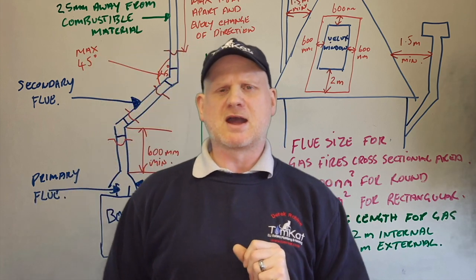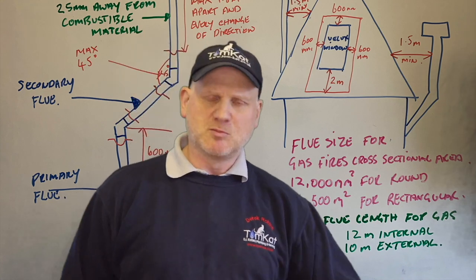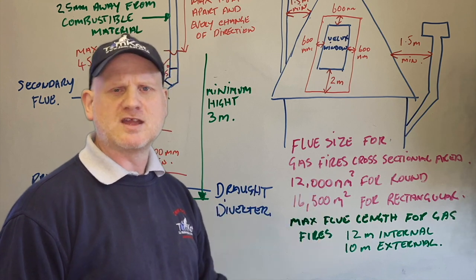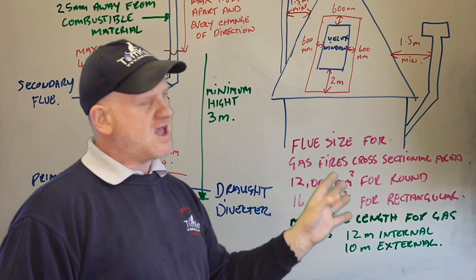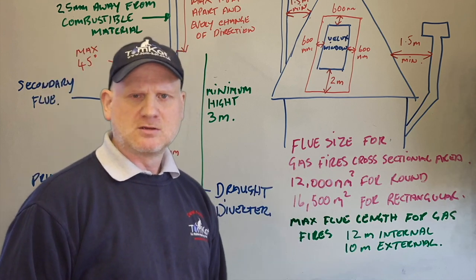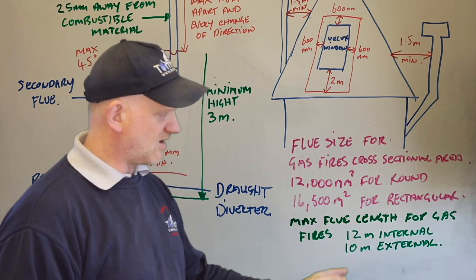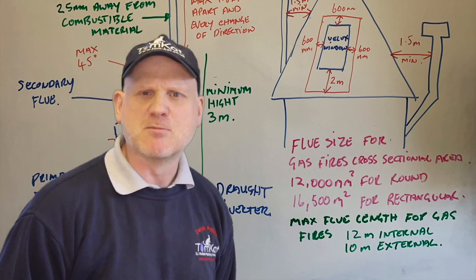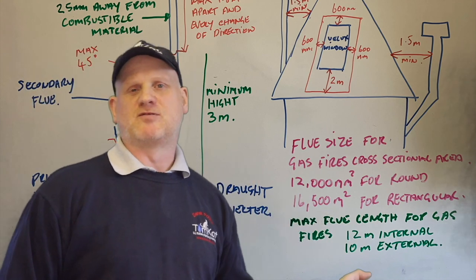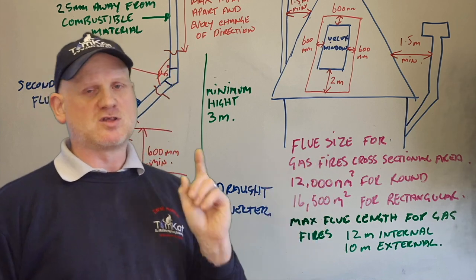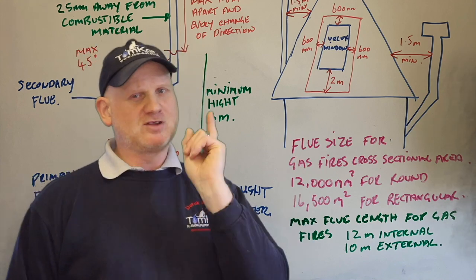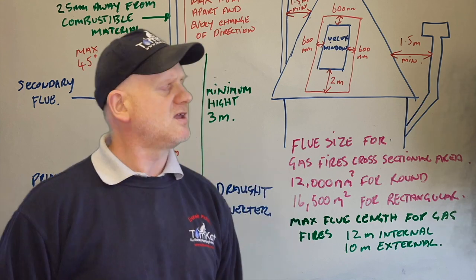That covers the main things for an open flued boiler. For open flued fires, the cross-sectional area for a round flue is 12,000mm² and for a rectangular one it's 16,500mm². The maximum flue length for a fire internally is 12 metres and externally is 10 metres. Remember, if it goes outside and is longer than 3 metres, it still needs to be insulated.